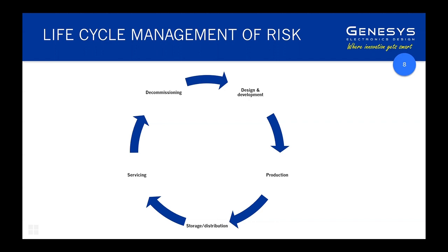So just to emphasize life cycle, this means the start from design and development, and most engineers would really focus on that and think, oh, design and development's done, the risk management process has ended, but you can see that's only one step on the pathway, albeit a pretty big step. But as Sue indicated, you have to apply the risk management process to production, so the manufacturing of the medical device itself. Its storage and distribution, so that would consider things like shelf life and temperature coverage, and whether the sterile device, for example, maintains its sterility or whether that's threatened.